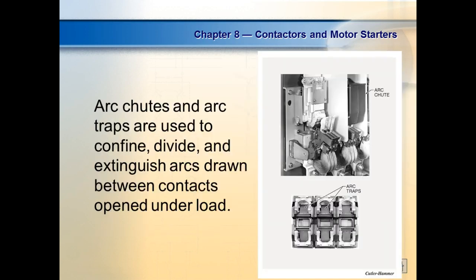So what we do is we isolate these things. These relays that I passed around, that little control relay, those contacts are open up to the atmosphere. Our new relays, you won't see those things anymore. They seal those contacts up. They put them inside what we call arc chutes. They put them in their own little troughs. They isolate them and then they put some type of plate on top of them. So they isolate the contacts from each other.